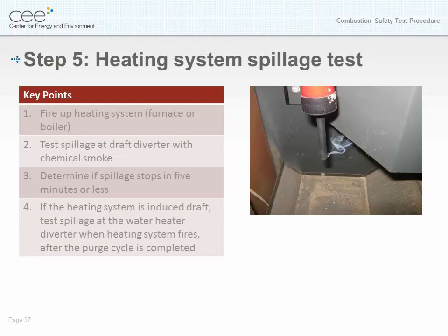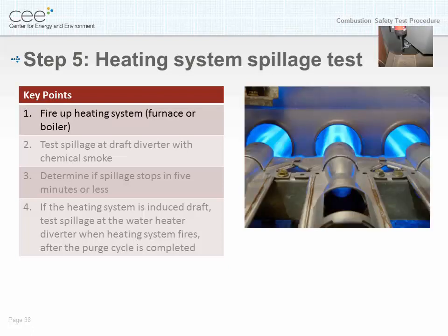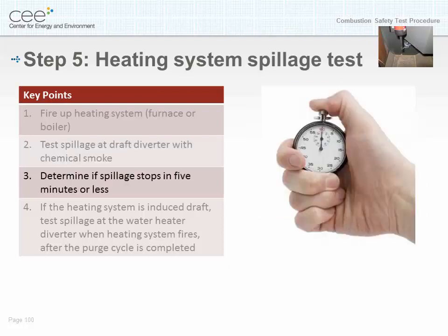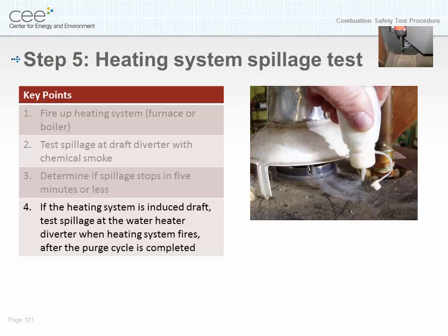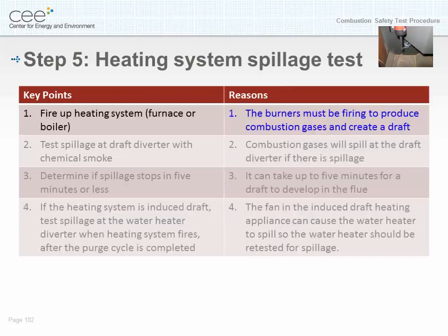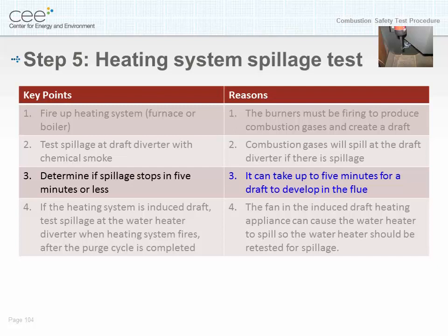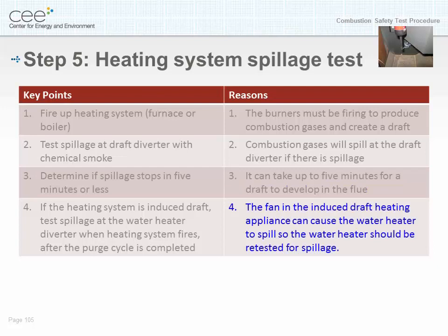Step five: heating system spillage test. Key points: number one, fire up the heating system — the furnace or the boiler; number two, test for spillage at the draft diverter with chemical smoke; number three, determine if spillage stops in five minutes or less; number four, if the heating system is induced draft, test spillage at the water heater diverter when the heating system fires after the purge cycle is completed. Reasoning: burners must be firing to produce combustion gases and create a draft; combustion gases will spill at the draft diverter if there is spillage; it can take up to five minutes for a draft to develop; and the fan in the induced draft heating appliance can cause the water heater to spill, so the water heater should be retested for spillage.